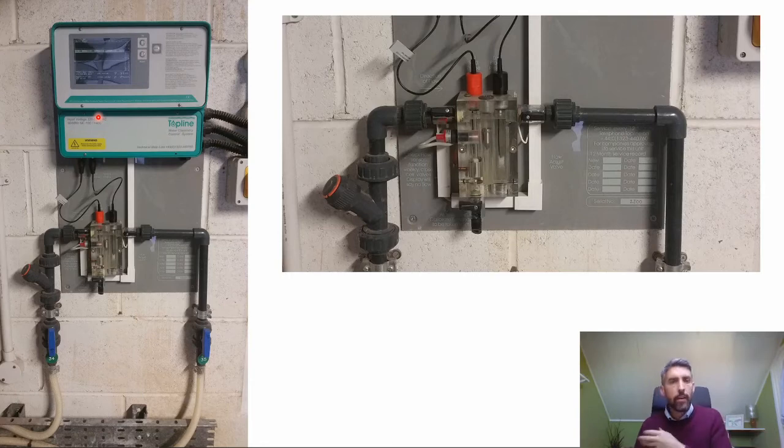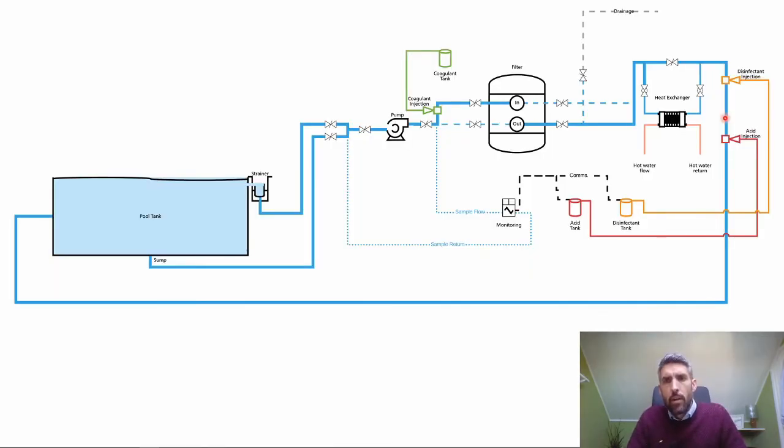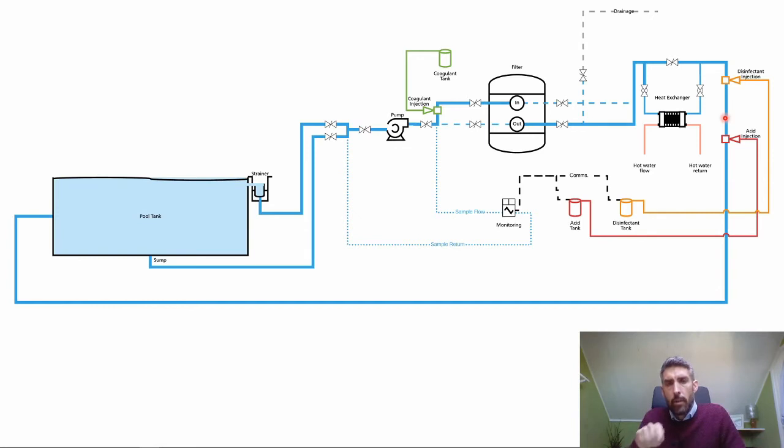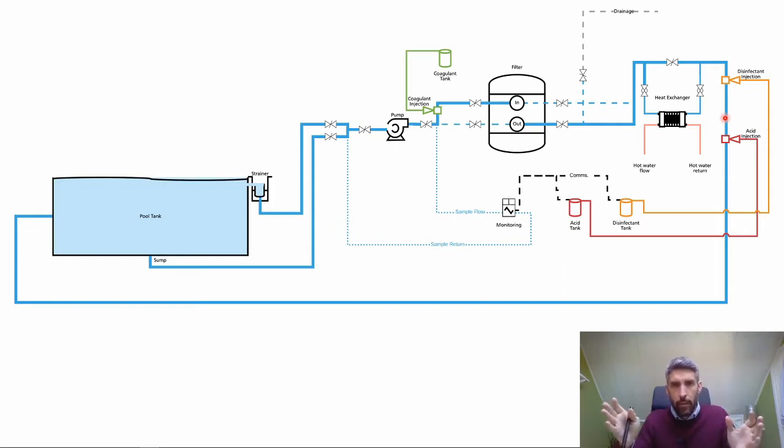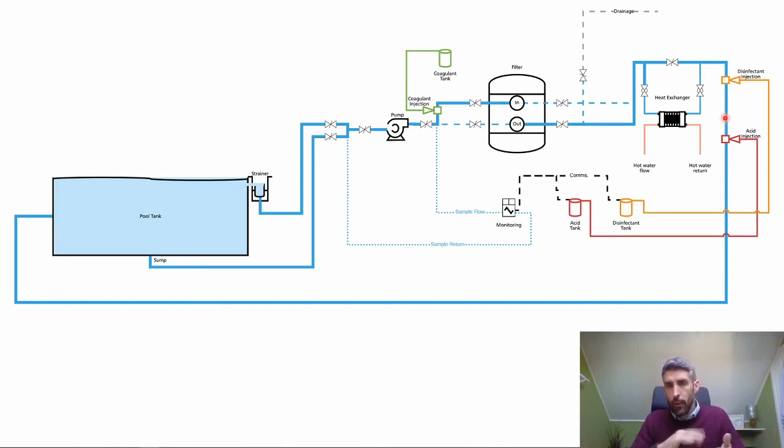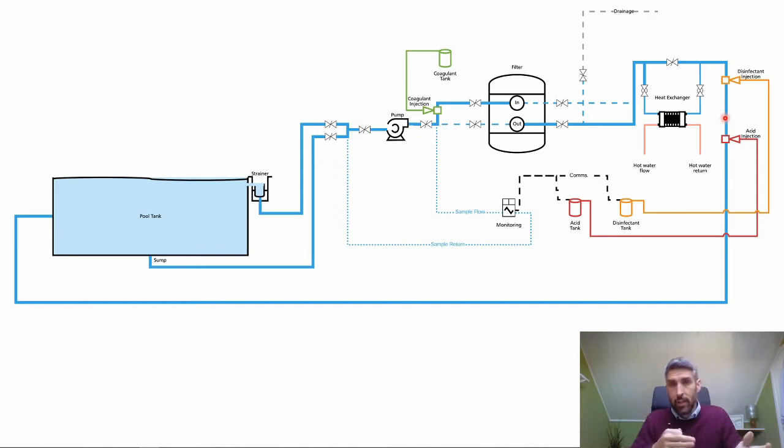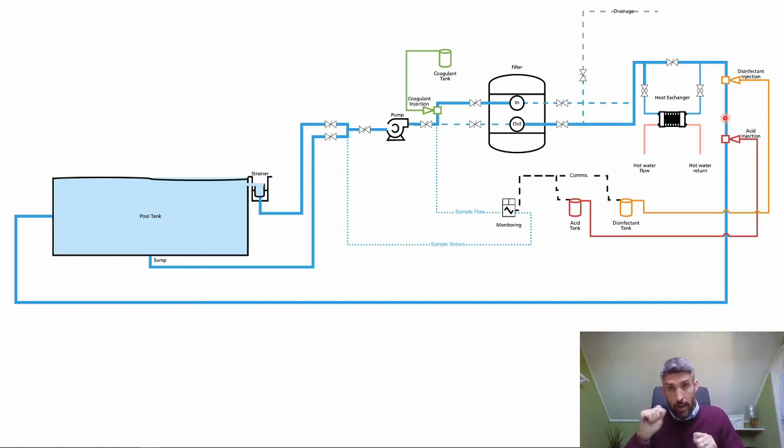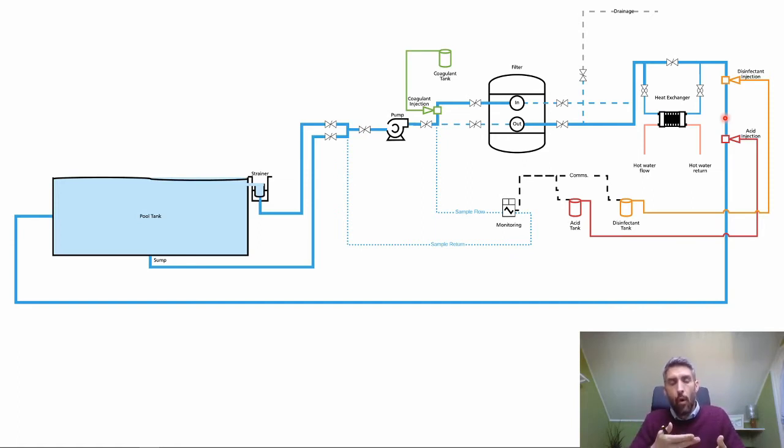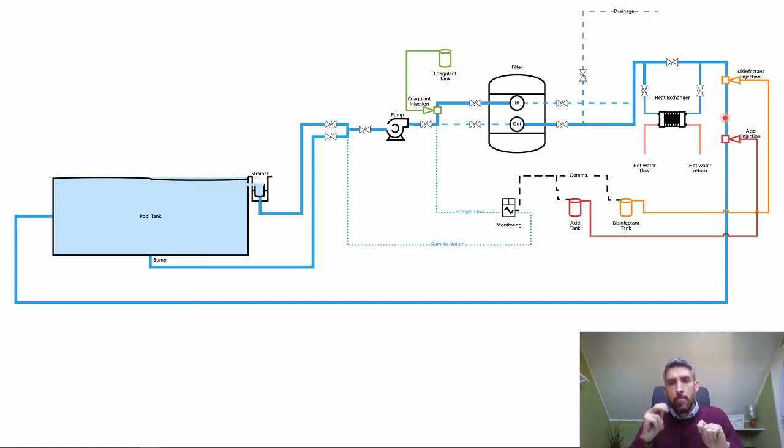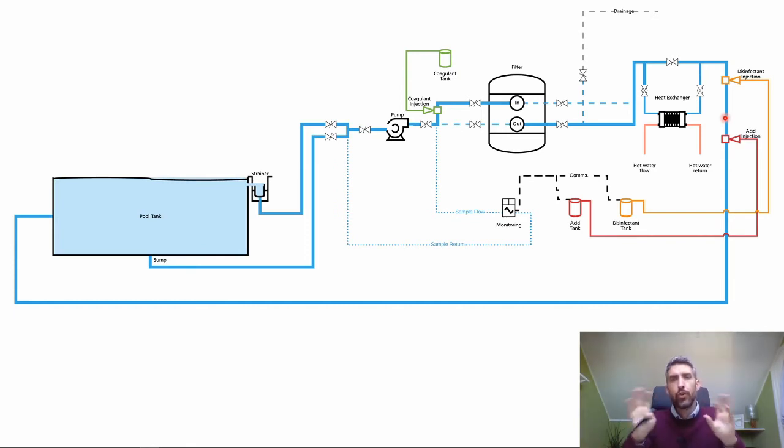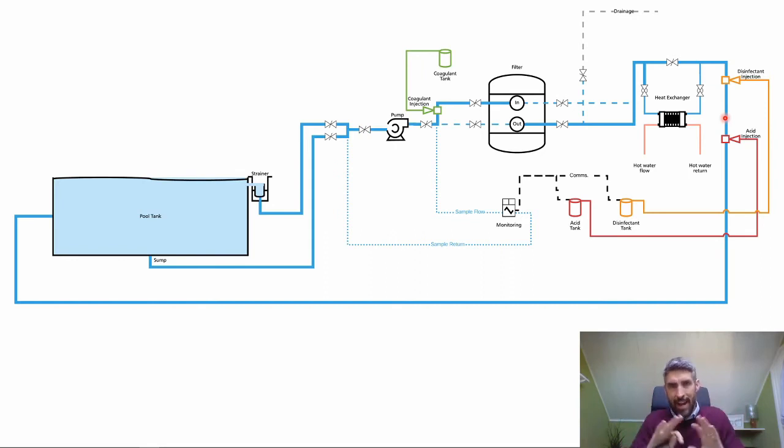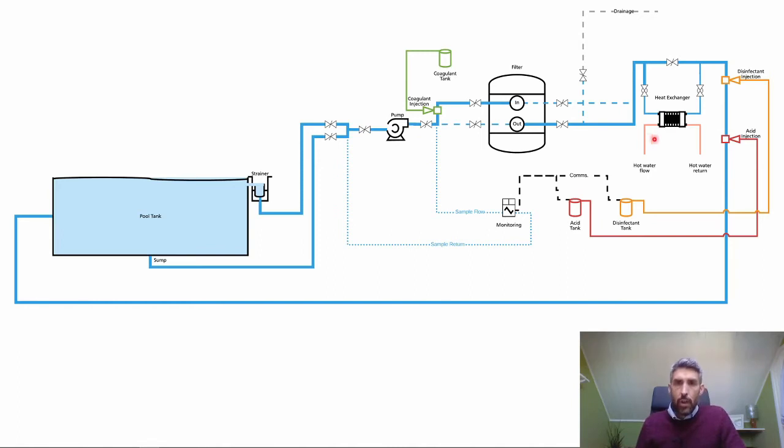The interlock needs to be double-checked. What we would recommend is whenever you're turning off the power supply to the circulation pumps, bookend the procedure with chemical dosing off, do what you need to do in the plant room, and then the last thing you do is put the chemical dosing back on. You're actually turning off the power supply yourself manually. Either that or write into your procedure that you must check that the interlock system has actually worked—don't just assume it's going to work all the time and never fail.